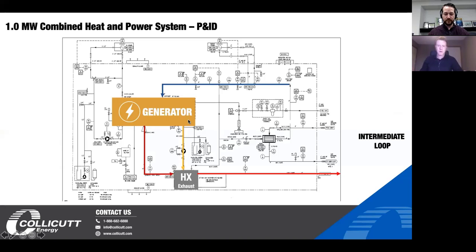So you can see how the arrows are trying to indicate temperature differences. You have cold water coming through. It's now been heated up a little bit. Then it comes into this heat exchanger here, where we're adding more heat, and the temperature rises through the heat exchanger. Then it comes to this heat exchanger here, which is called the CHP heat exchanger. This is where we transfer the heat from the CHP to the building. And I'll just pull up the last arrows. On the other side of the heat exchanger, we have cold water coming from the building through this heat exchanger and then going back.